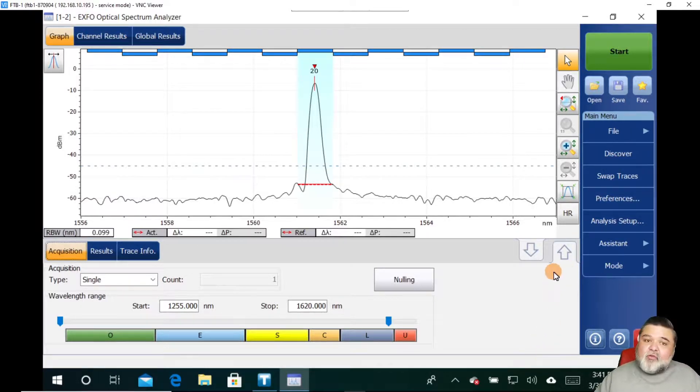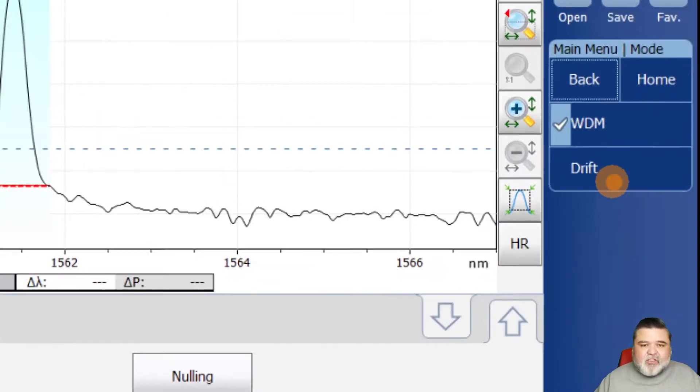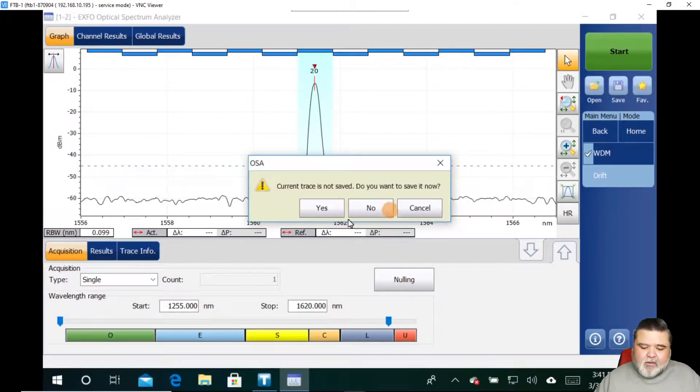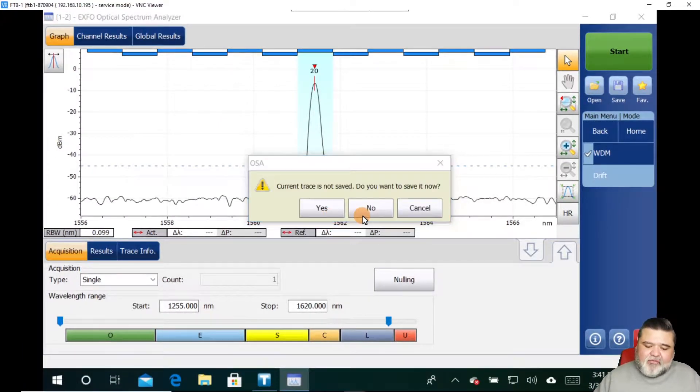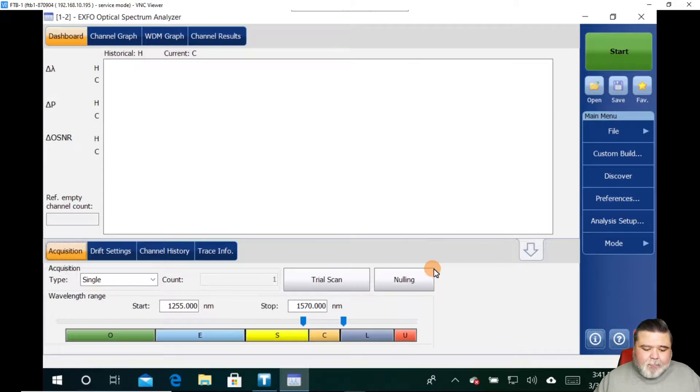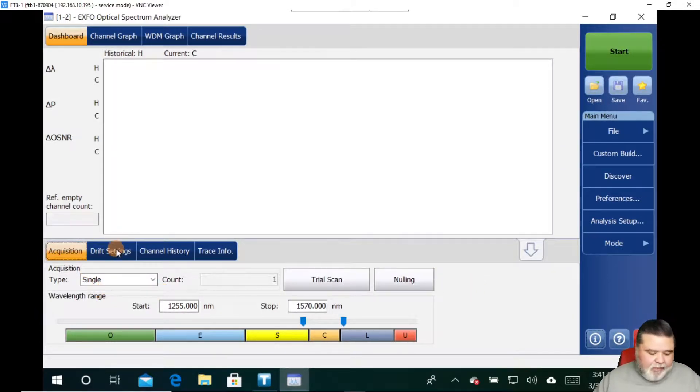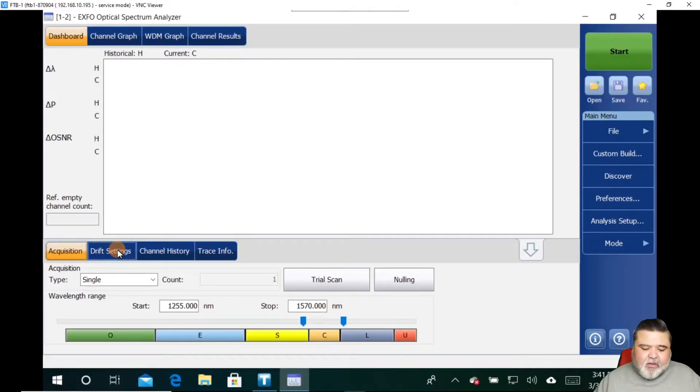If I wanted to do a drift test over time, I can go over here to where it says mode. If I select mode and I switch from WDM to drift, I'm now doing a drift test. We're transitioning over to that.